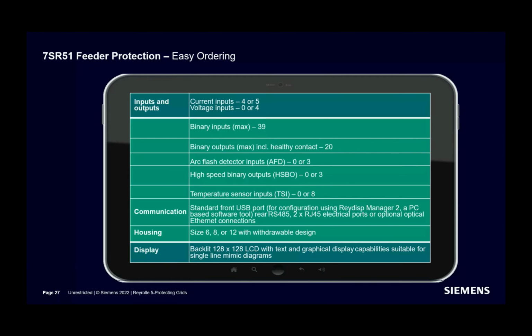So when you choose the 7SR5 overcurrent protection relay, you will have the option of choosing 4 or 5 current transformer inputs, depending on the requirement. And you can choose the CT only version or CT plus 4 VT voltage transformer inputs as well. Now it has up to 39 binary inputs and 20 binary outputs available. 3 binary outputs can be provided as high-speed binary outputs separately from arc sensor inputs. So you have 3 high-speed binary outputs in the normal binary output set.